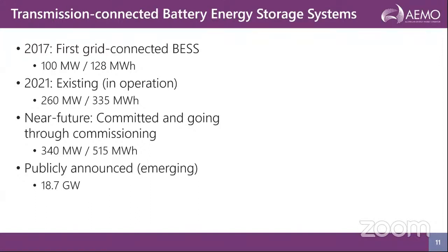And at the time of connection, it was the largest transmission connected lithium ion battery, popularly known as a Tesla battery. Those of you who read the news, it's often mentioned as Tesla's big battery in South Australia, but it is registered as Hornsdale Power Reserve. And recently it has expanded to 150 megawatt, 194 megawatt hour capacity. Currently, as we speak, we have 260 megawatt of transmission connected batteries in operation in South Australia. Well, I should say it has increased by 300 now, because earlier this week, the 300 megawatt battery, often known as the Victorian Big Battery, went into commercial operation.